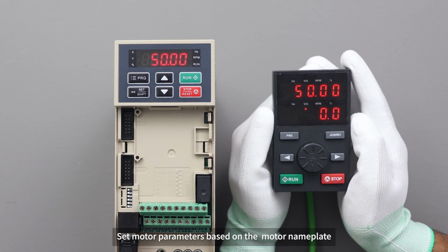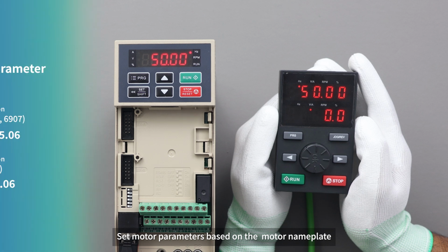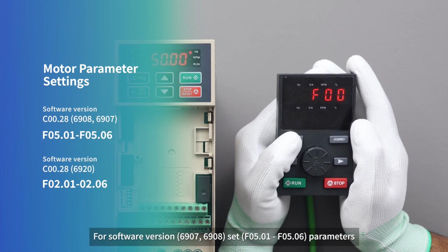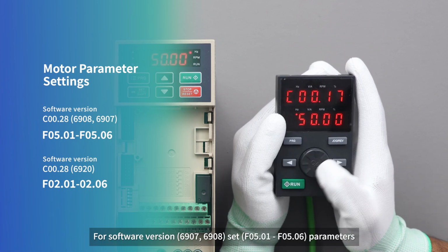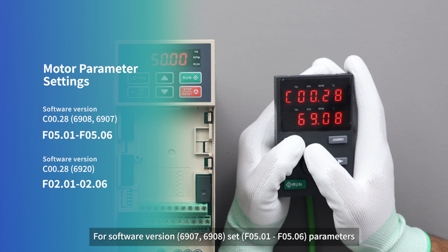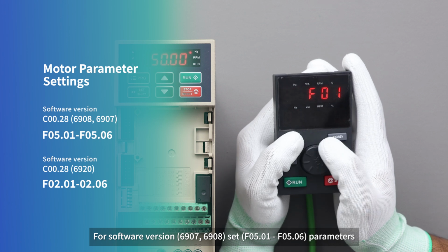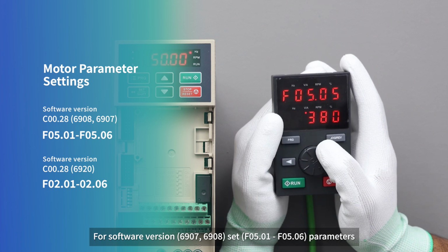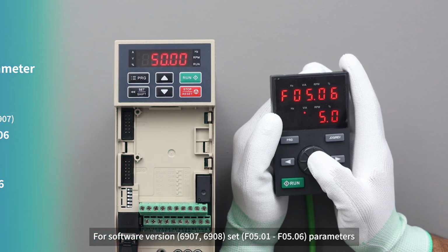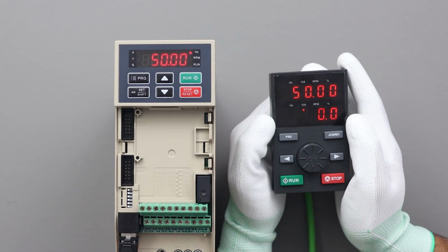Motor parameter settings. Set motor parameters based on the motor nameplate. For software version 6907 and 6908, set F0501 to F0506 parameters.